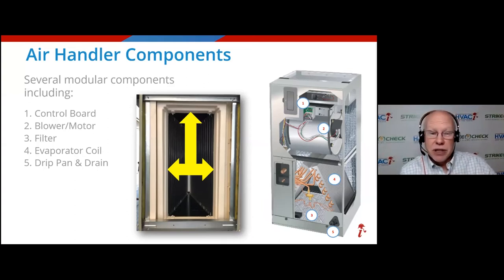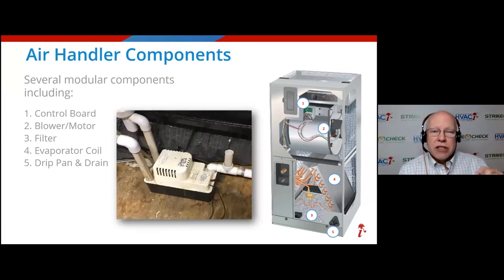If you don't put in a filter and you get a lot of dirt and debris on the A coil, it drips into the drip pan and then you get a water loss because your drip pan is all clogged up and it overflows. And if it's in the attic, you know where the water ends up: your dining room table. You normally drain that off to a drain or to the outside if you're in a place to do that. But if you're not in a place to do that, you use a condensate pump as seen here.